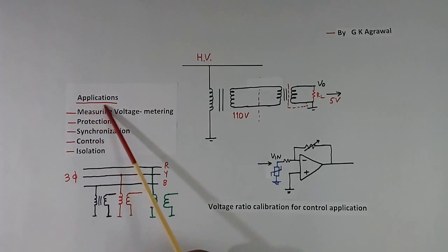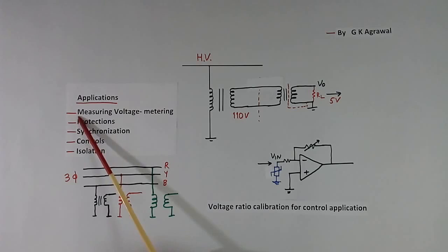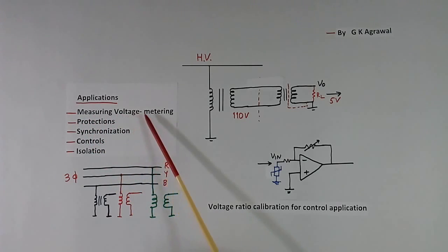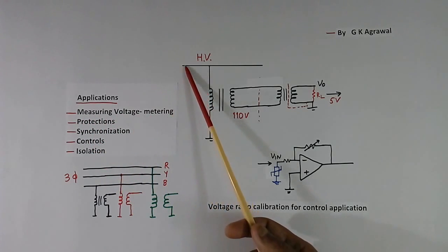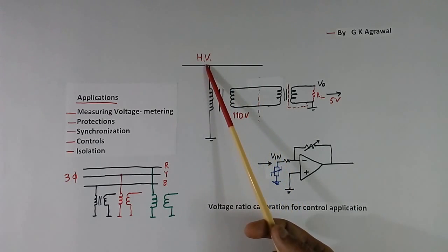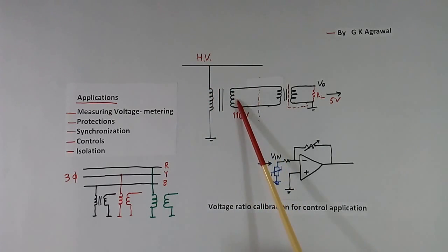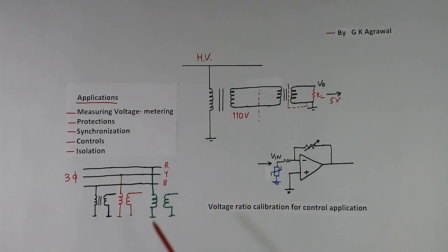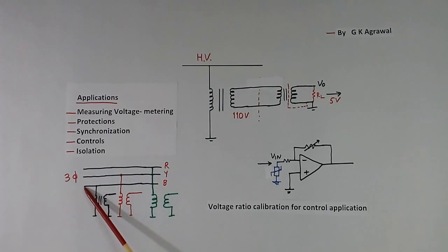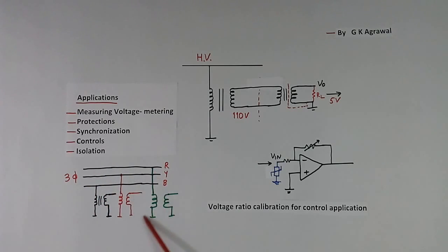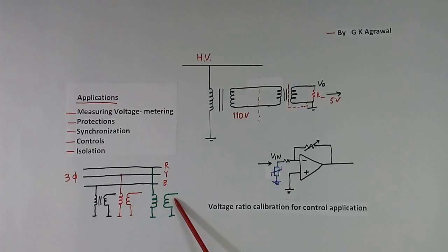Now we come to applications. The first application is measuring voltage — metering. We want to know what is the voltage at a high voltage point, so we connect a PT and at the secondary we connect a voltmeter. I have shown single phase here, but generally power supply in industries will be 3-phase. For 3-phase, we connect 3 PTs — shown here in black, red, and green colors — and 3 voltmeters, or there will be 1 voltmeter with a switch.